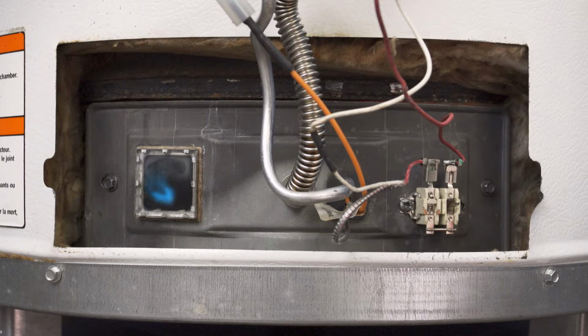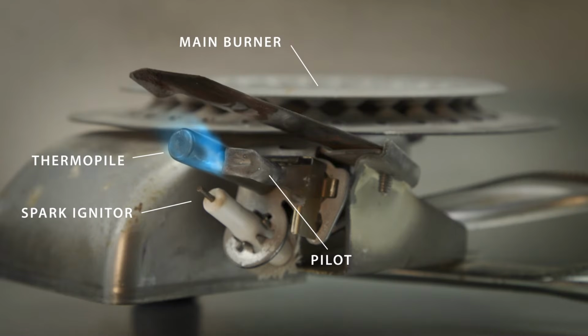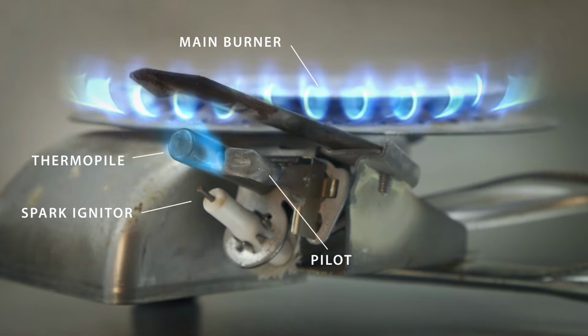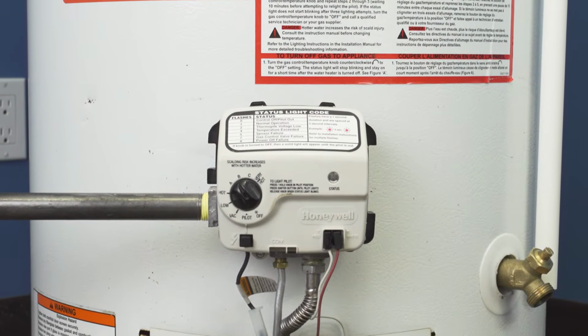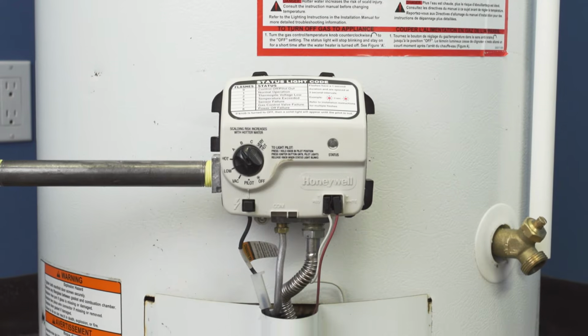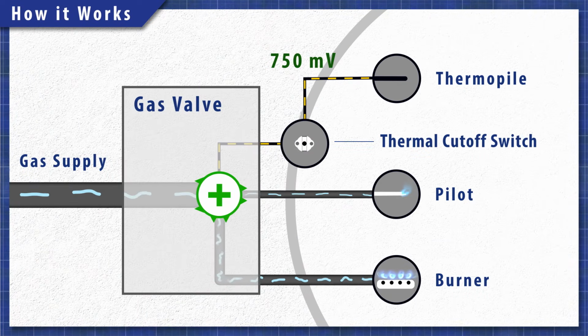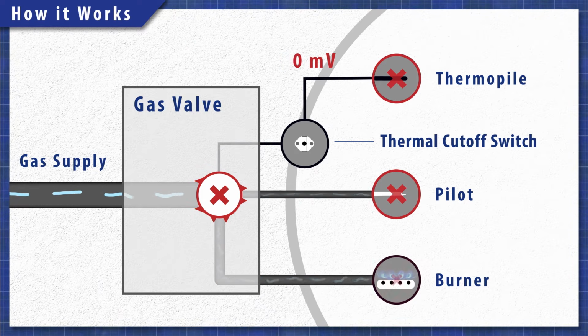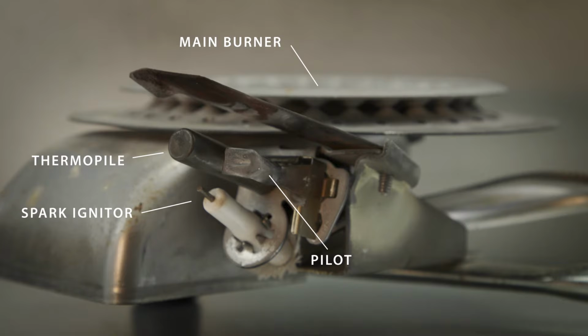Standing pilot water heaters use a pilot flame that burns continuously and will ignite the main burner whenever heat is needed. Next to the pilot is the thermopile, which generates a small electrical current when heated by the pilot flame. This produces less voltage than a AA battery, but enough to power the electronic gas valve and diagnostics. The thermopile also acts as a safety switch. If the pilot light goes out, then the thermopile will cool down. The voltage will drop, and the gas valve will shut off. This prevents unburnt gas from being released into your home. Now, if the thermopile is faulty, then it will also prevent the pilot from staying lit.